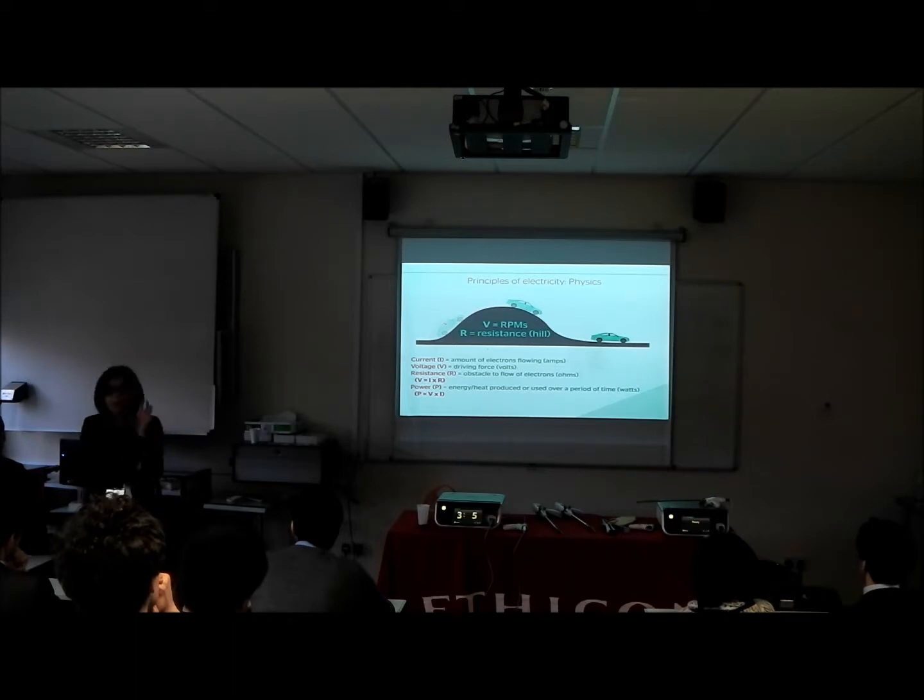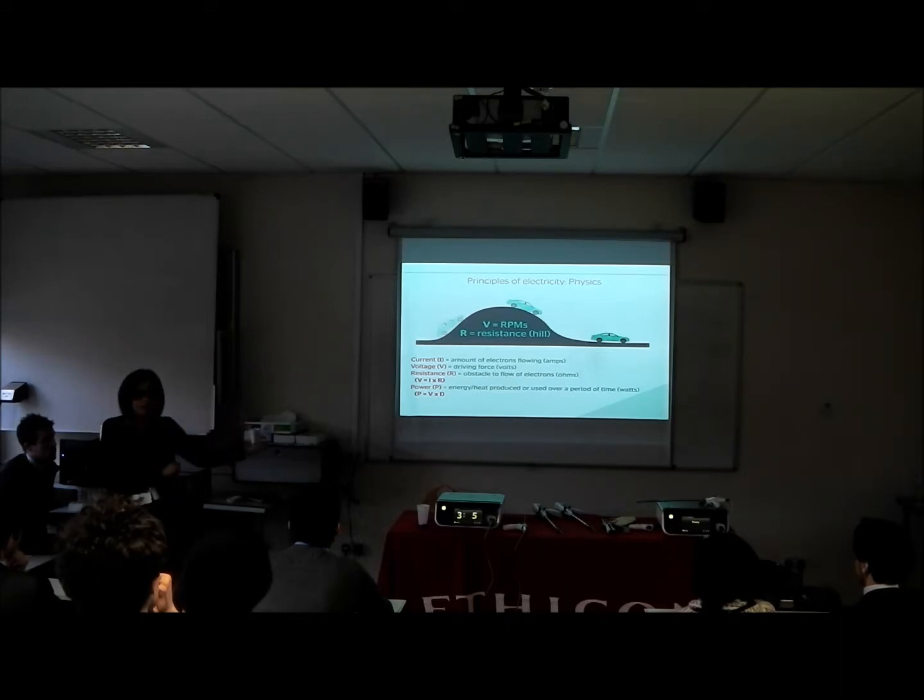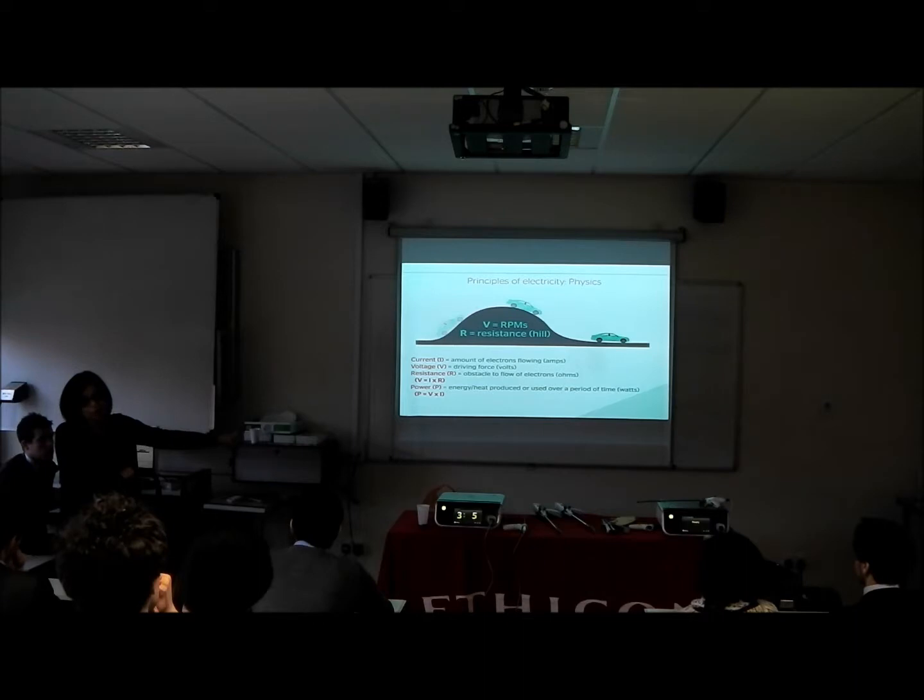Now, when you look at household appliances, you will know that the voltage is constant. So we get electric current at 220 volts. Does everybody know that? When we use electrical energy in patients, the power remains constant. We set our generators at a particular power that we want to use, but the voltage changes. And that is a very important point which you will realize as we go on further.